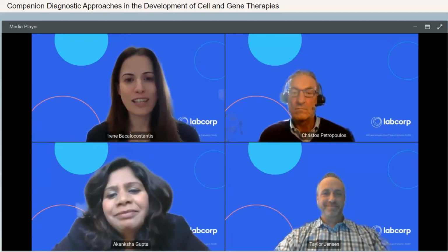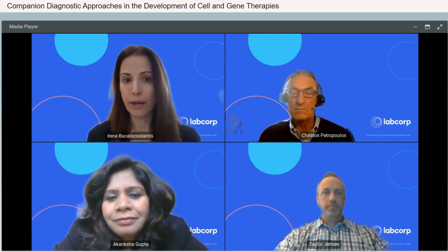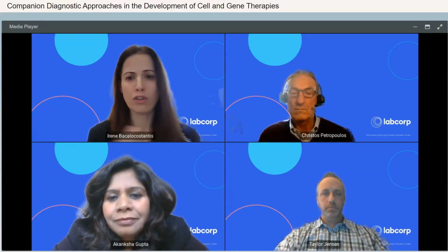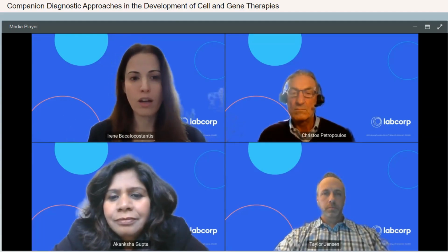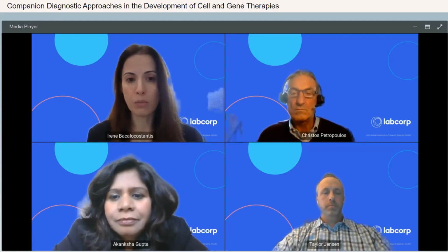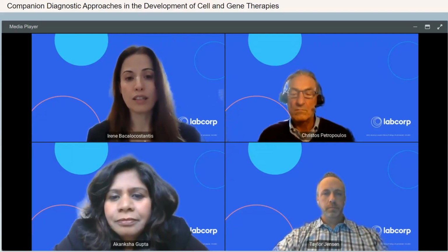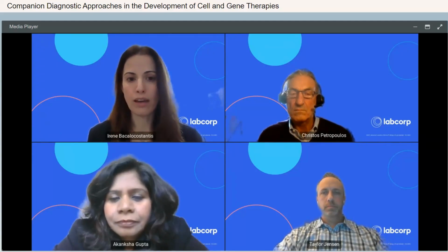But at the initial stages, the diagnostic manufacturer must select the notified body to review their technical file. And we do this years prior to the expected approval. So at least 2 years ahead, we will go in and connect. As LabCorp, we have our notified body that we work with, and we will inform them of this pending submission. If a facility doesn't have ISO 13485 certification, of course our CDX sites do, then you would need to work with them as well for that certification.